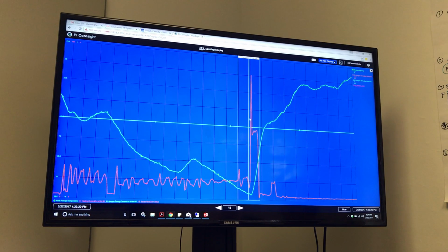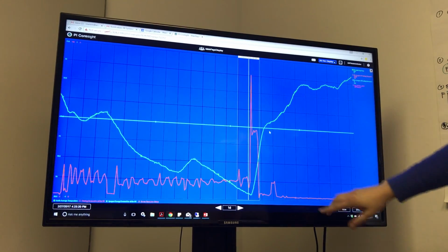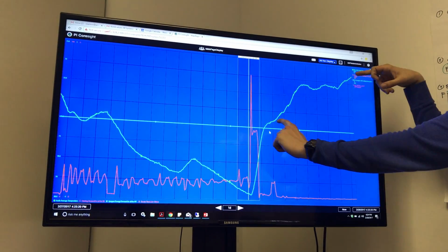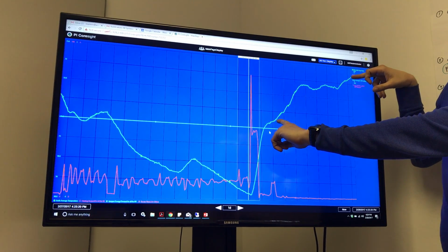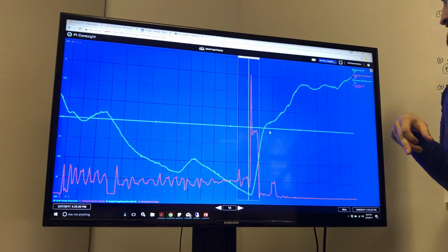So basically, it took us from 7 a.m. 1 hour, and then a little bit, and we reach our set point around 72. And since then, all of this is just internal gain. We have not provided any heating. What's the outdoor temperature, by the way?